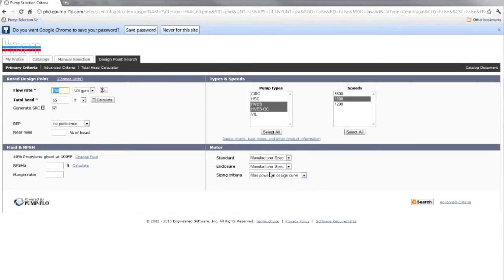And then the sizing of the motor. This is kind of going back to what we talked about before. Do we size the motor for that operating point, or do we size it so it's non-overloading across the entire pump curve? Or do we not have the program size the motor at all? We've got all of these options. Just for this application, let's have it selected for maximum power on the design curve. We could have it select for the maximum power on the maximum diameter, which gives the biggest motor that pump would ever use. But we're going to do the max power on design curve. We're only interested in what our curve requires. So now we've got all of this plugged in. We know we're going to be picking a horizontal end suction pump, whether it's split coupled or close coupled, we'll determine that, and with these conditions.